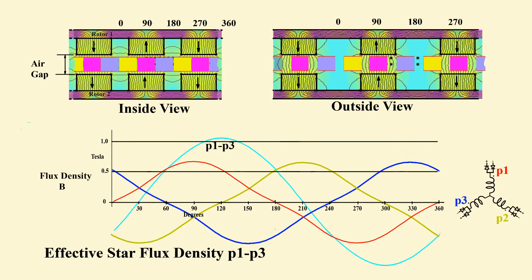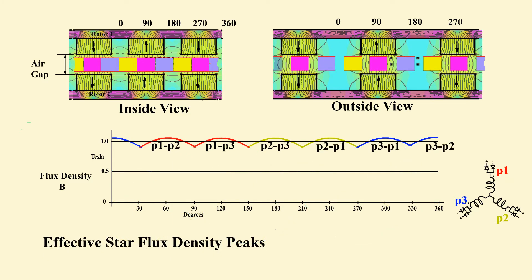Effective values for star connection are given by subtraction of phases. For example, phase 1 minus phase 3 is shown here. The result is a near perfect sine wave due to total elimination of third harmonic content. Taking the highest absolute value of the subtractions gives a waveform proportional to the machine's loaded, rectified voltage.